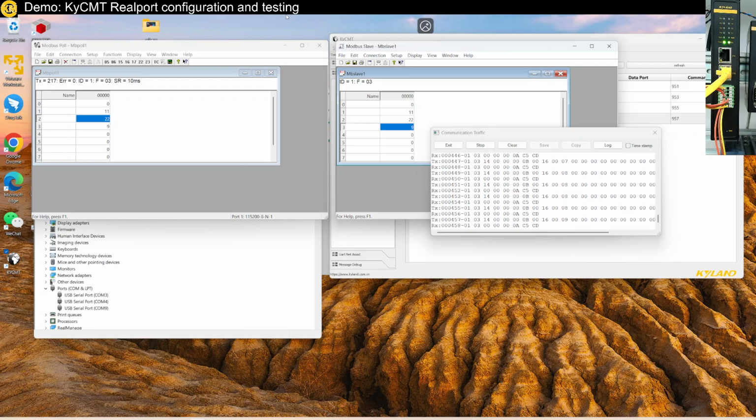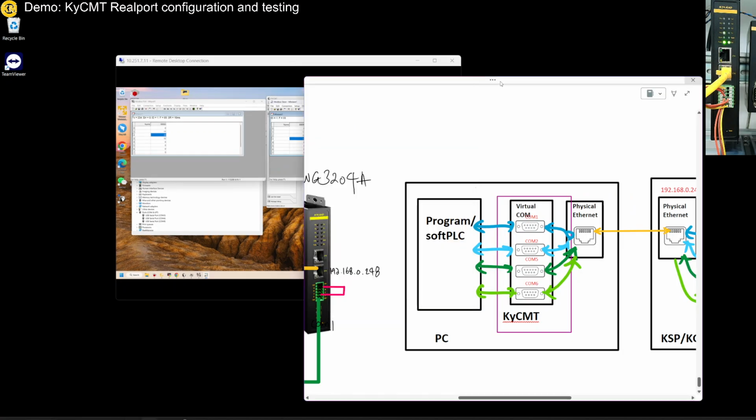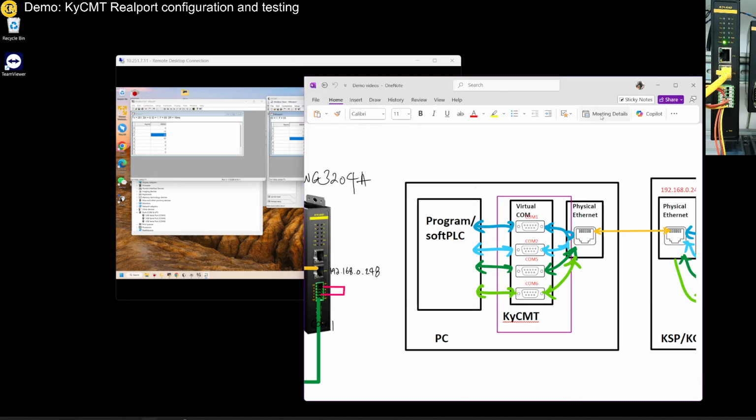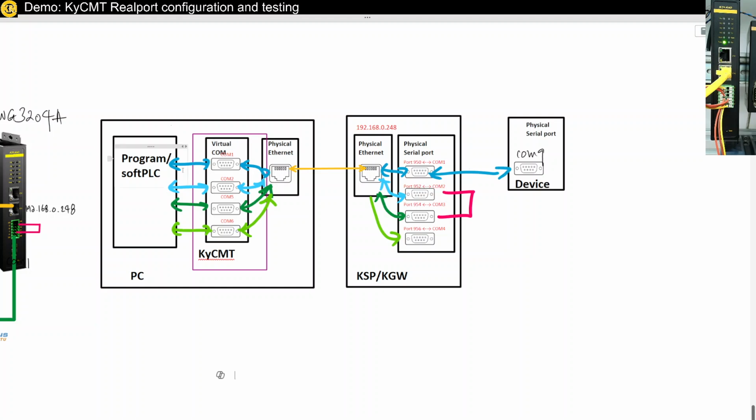Okay, this is good. So that is the test of using Modbus TCP/IP from here, port 1 to port 9. Port 9 replies back to port 1, then goes back to port 1 again. Okay, but what I'm going to do next is, what if I reach out to COM2? You will go to COM2, because I'm putting up a loop over here.